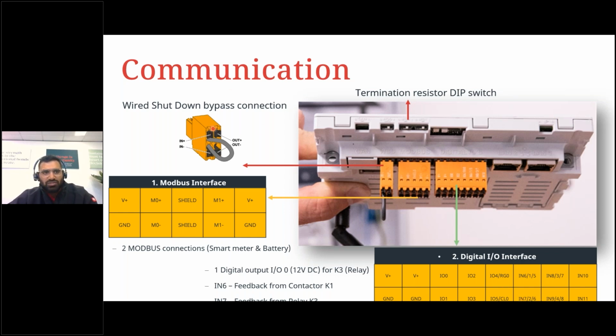So this wired shutdown is the other part. By default, they come with a bypass connection. If you were to remove it, the inverter will go into standby. So please be careful that you don't remove it in a normal installation. And this is normally used when you want to run the system with a genset, to put the inverter into standby when the genset is running. We'll be also taking a look at that.